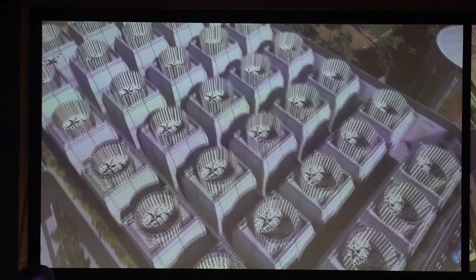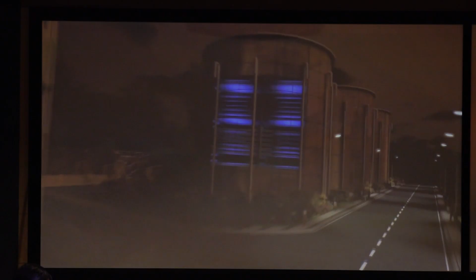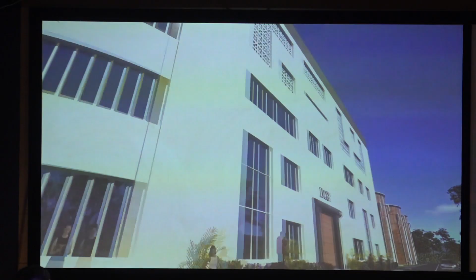The returned water will be carried back to the DCS plant to reject heat using cooling towers. Additionally, thermal storage will be charged during night hours between 10 p.m. and 6 a.m. for better night demand management. DCS by design will overall improve efficiency, conserve energy, save space, and reduce environmental impact.